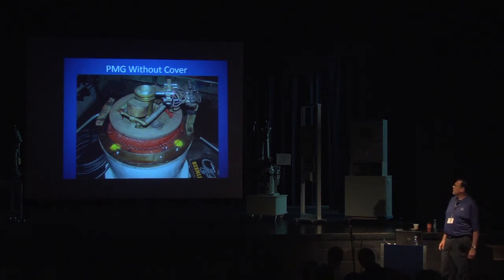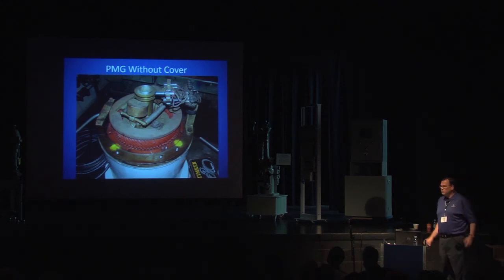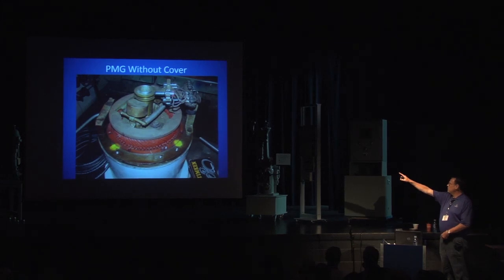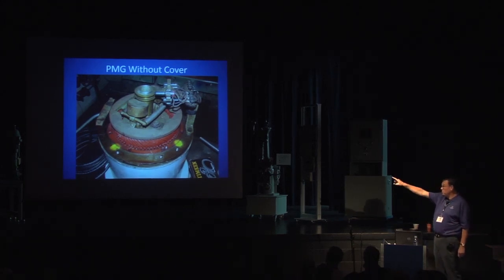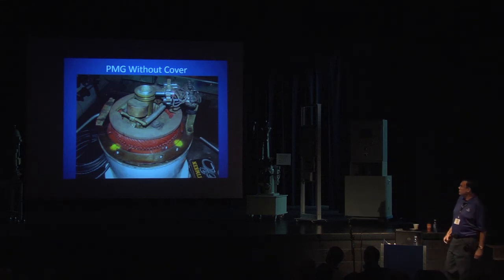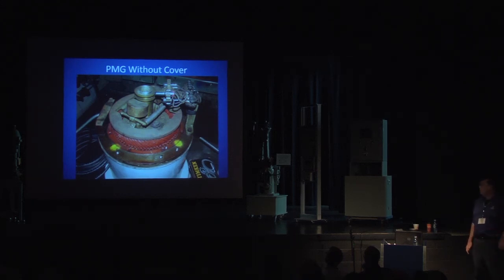This is very bad. You get dirt, dust, and carbon dust off your exciter all in the works here, and there are mechanical parts that move. That ball there is the overspeed mechanism, which is very important, and it needs to work and not be clogged up. Well, the covers are so heavy, and some of them are.